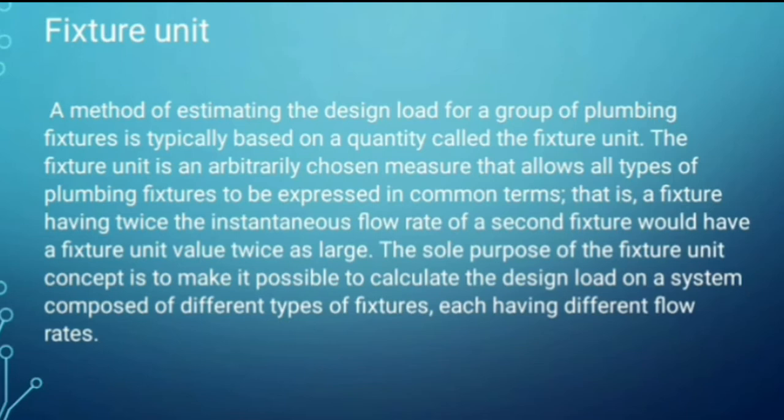on a system composed of different types of fixtures, each having different flow rates. It's a unit of measure based on the rate of discharge, time of operation, and frequency of use of a fixture that expresses the hydraulic load imposed by the fixtures on the sanitary plumbing installation. Fixture unit is used in plumbing design for both water supply and wastewater.